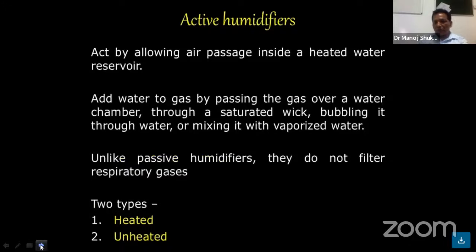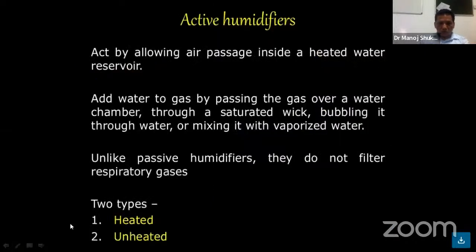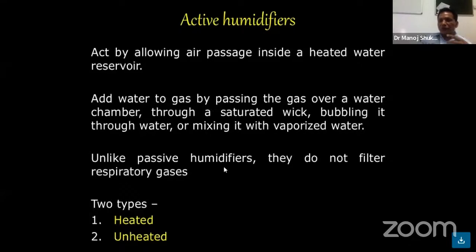The active humidifier works by allowing the airflow inside a heated water chamber, and adds water to gas by passing the gas over a water chamber, through a saturated wick, by bubbling it through the water, or by mixing it with vaporized water. Unlike passive humidifiers, they do not filter respiratory gas. Active humidifiers come in two kinds: heated and unheated.